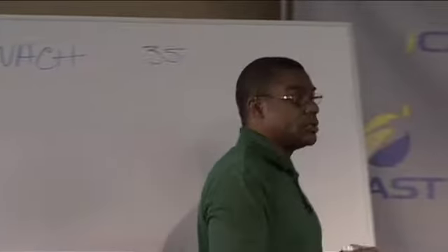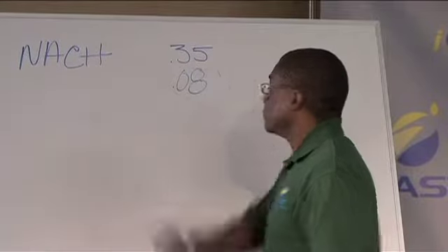BPI recommends 0.35, which is 35% of the air in your house exchanged every hour in order for your house to feel comfortable. That was the reading I got on his house: 0.08. So I asked him, does your house tend to feel stuffy?